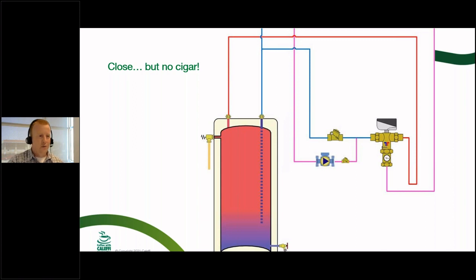And so what you're going to find here with this particular setup is the recirc is going to come back, and it's going to go into this T right at the cold inlet, and the only place it can go is to the cold inlet of the mixing valve, because they had a swing check that was installed right just upstream, which is very similar to the drawing that I just showed you. Okay, but in the drawing that I just showed you, the recirc actually tied in right here and went back to the domestic hot water source. And so when I got this call, I said, you know what, really, you should be looking at tying in from the recirc back to the domestic hot water source, or coming back from the recirc outlet there on that circulator back to the cold inlet of the domestic hot water source.